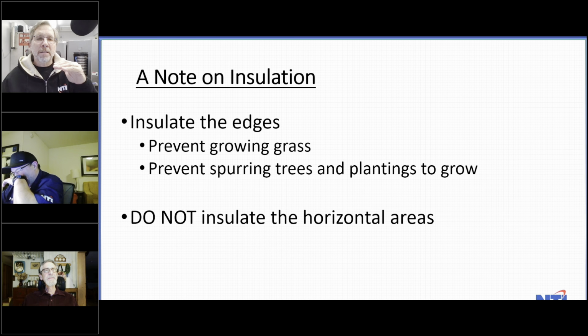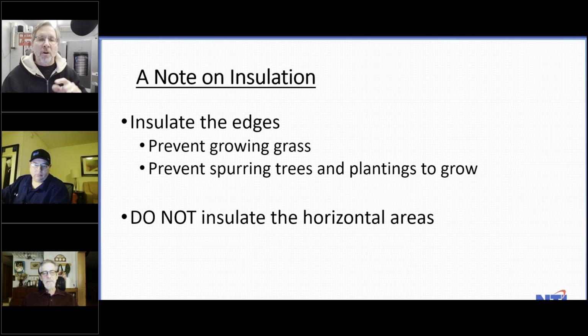It gets cold out at night. We get a nice misty haze, we get dew on the ground, right? But the surface temperature or the dirt underneath the grass is keeping it from freezing. But if you've insulated your walkway, it got cold overnight and dropped below freezing, and now it's a fine sheet of ice, because the ground temperature can no longer get there. Now you've made an ice rink that people are going to slip on, because your snow melt control cannot feel the moisture and cannot feel that it needs to turn on, and you're screwed. You're going to cause big problems.